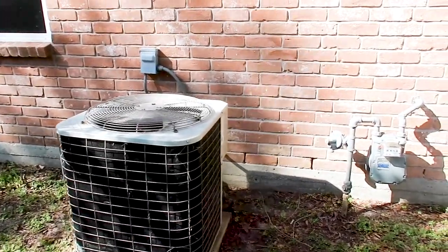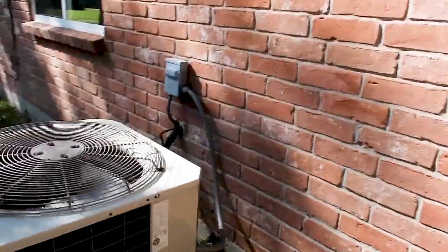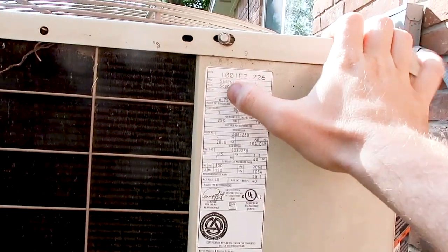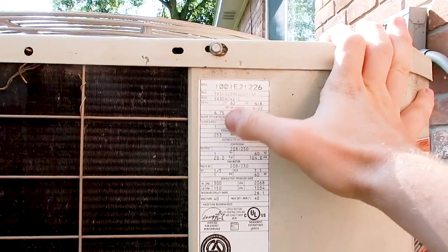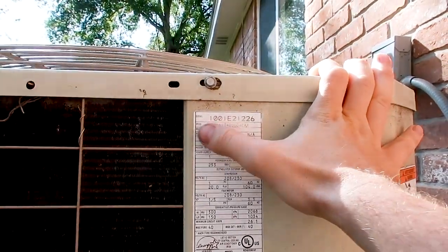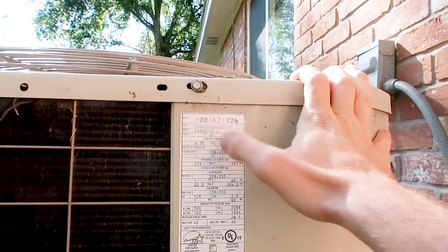You always want to pull the data off the data plate here. This is a carrier unit or a Bryant unit. In the serial number, it's always the second two numbers, so this is a 2001. You do numbers divisible by 12 and 6, so this is a 42, meaning 3.5 ton. And it also has R22 Freon.